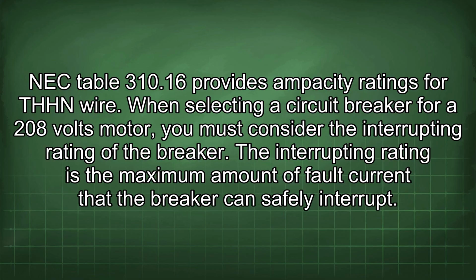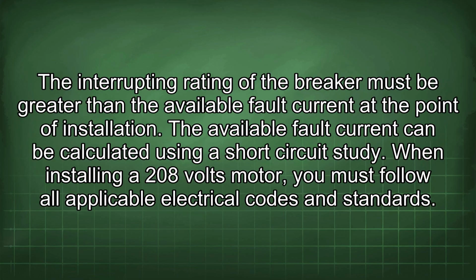When selecting a circuit breaker for a 208 volts motor, you must consider the interrupting rating of the breaker. The interrupting rating is the maximum amount of fault current that the breaker can safely interrupt. The interrupting rating of the breaker must be greater than the available fault current at the point of installation.